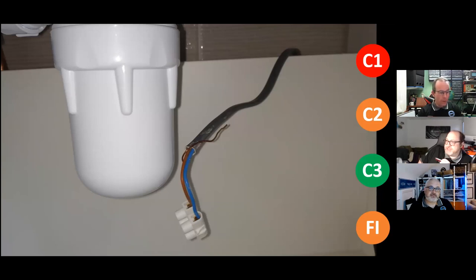I would often think C2 due to the reduced size, but readily accessible under a cupboard where children may go elevates that to C1 for me. And in a bathroom as well. In a bathroom. Yeah, so C1, I think that's fairly... Sean has said it just needs enclosing appropriately. Absolutely right, Sean, it does.